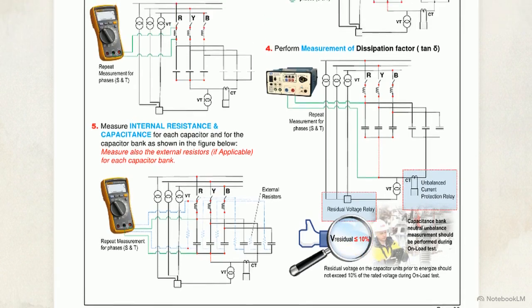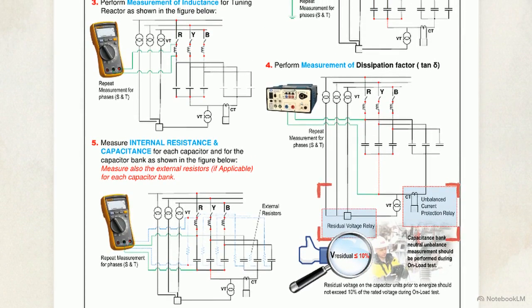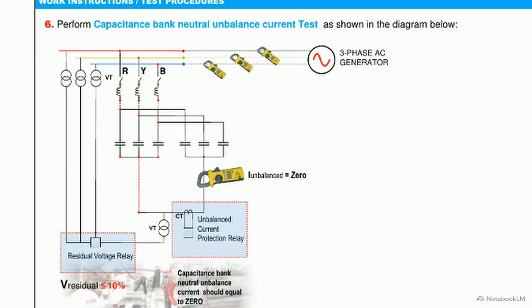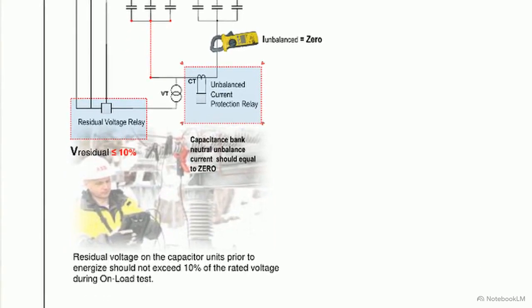Step 8 confirms the residual voltage and unbalance-relay circuits are connected and primed to read this decay during the on-load phase. Clearing this 10% threshold is the final physical barrier between the safely grounded hardware and a grid-connected system. We move to live state validation. The team connects a 3-phase AC source and diagnostic meters, as defined in the schematic. Under controlled conditions, the source is energized, and engineers monitor phase voltage and current continuously. This ensures the bank responds predictably as it accepts the load.